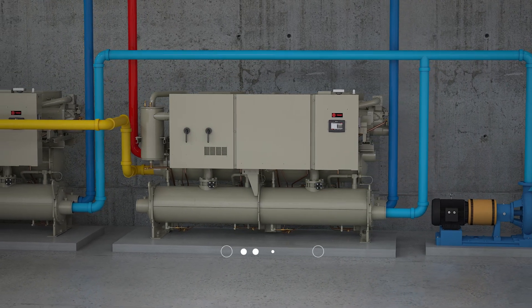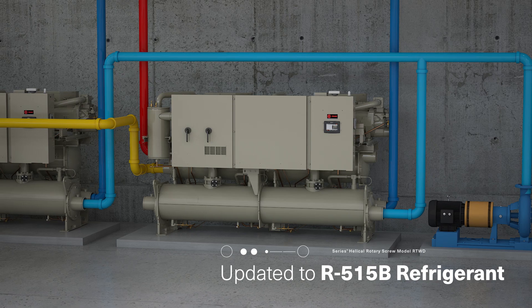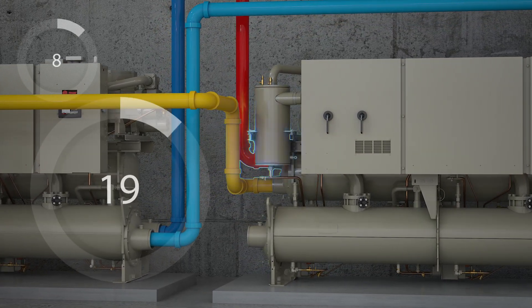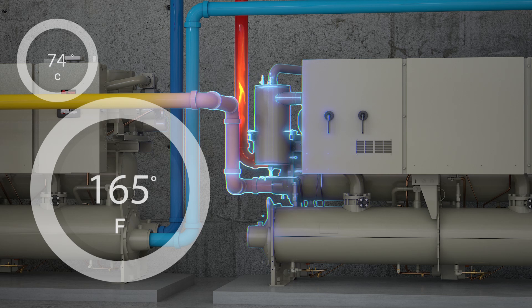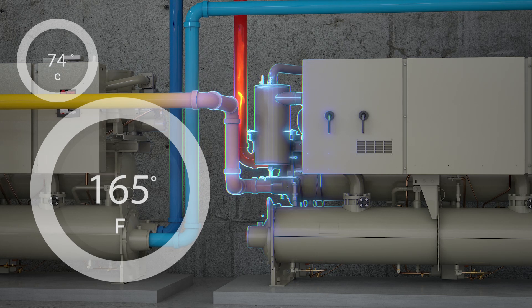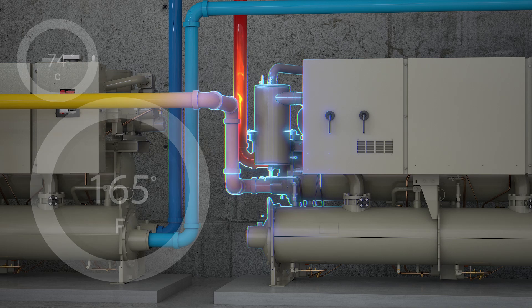The RTWD, for example, has been updated to R515B refrigerant for heating applications. R515B is not only more environmentally friendly, it also delivers hotter water temperatures of up to 165 degrees Fahrenheit, perfect in electrified heating applications.